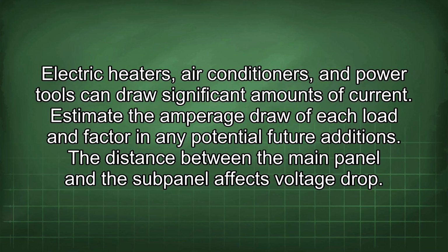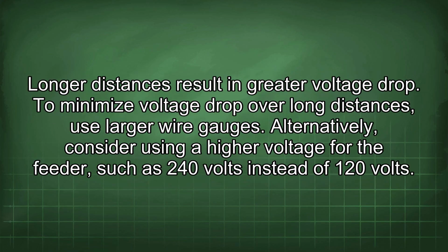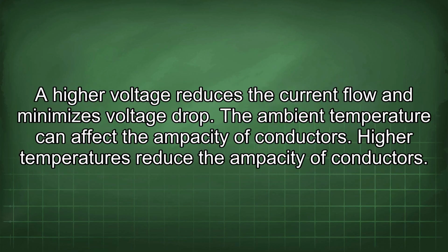The distance between the main panel and the subpanel affects voltage drop. Longer distances result in greater voltage drop. To minimize voltage drop over long distances, use larger wire gauges. Alternatively, consider using a higher voltage for the feeder, such as 240 volts instead of 120 volts. A higher voltage reduces the current flow and minimizes voltage drop.